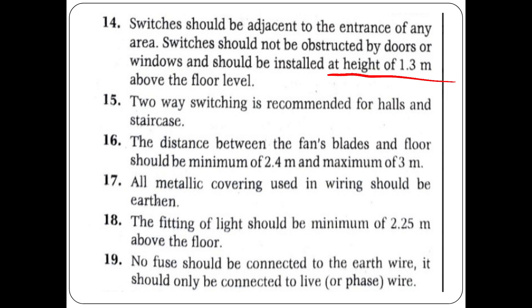Two-way switching is recommended for halls and staircases. The distance between the fan blades and the floor should be a minimum of 2.4 meters and a maximum of 3 meters.